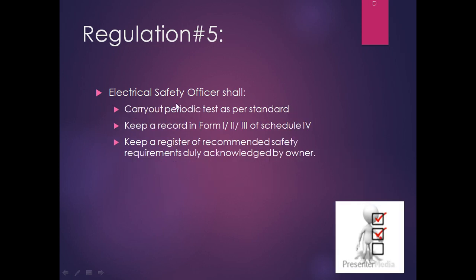The electrical safety officer shall carry out periodic tests as per standard. So he has to carry out the periodic electrical test for the installation, and he also has to keep a record in the form of form 1, form 2 or form 3 of schedule 4. So there is a schedule along with this CEA regulation 2010. Depending on voltage level, the electrical safety officer shall fill form 1, form 2 or form 3. These forms are a checklist kind of form.